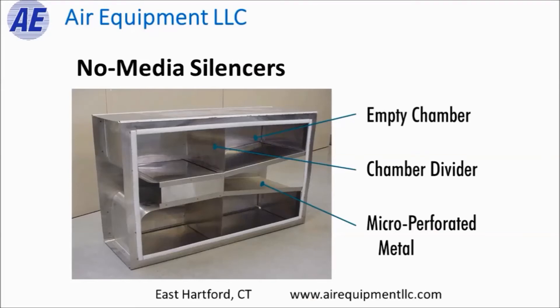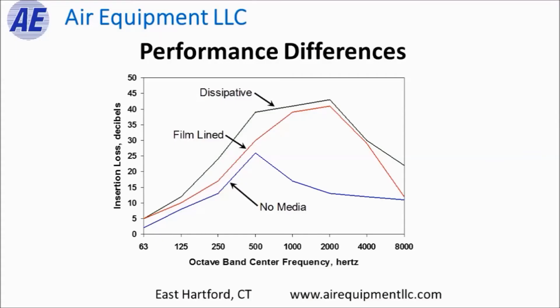The third type is the no media silencer, which has empty chambers. The perforated metal uses micro perforations — the theory is that sound energy enters one of the chambers, rattles around, and does not return to the supply air stream, attenuating some noise. A graph here illustrates the typical performance of all three different types of attenuators.